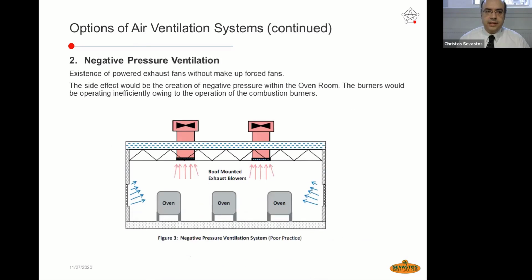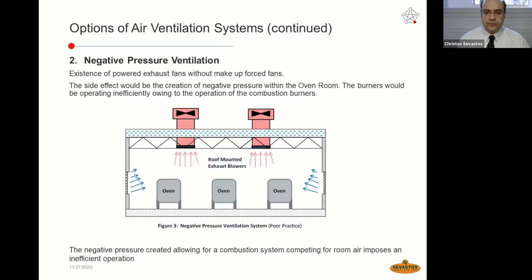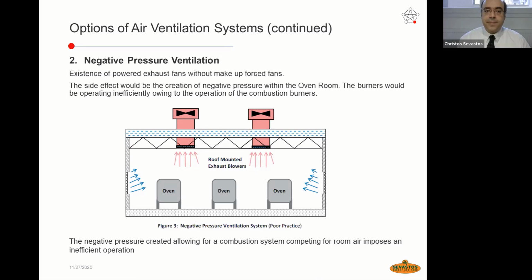A second option of ventilation is the negative pressure ventilation, for which we have been referring to the previous slides. Existence of powered exhaust fans on top instead of unpowered. The side effect will be the creation of negative pressure within the oven room, because we are going to have air supply from the windows, and the burners would operate inefficiently. The negative pressure created is allowing for a combustion system competing for room air which is imposing an inefficient operation. What does this mean? This means that the oven is competing for air because of the burners, and we are also extracting the heat with powered roof-mounted exhaust blowers. This is a negative pressure ventilation. This is often what is happening in areas with tunnel ovens, and this means that we are going to have an inefficient operation.